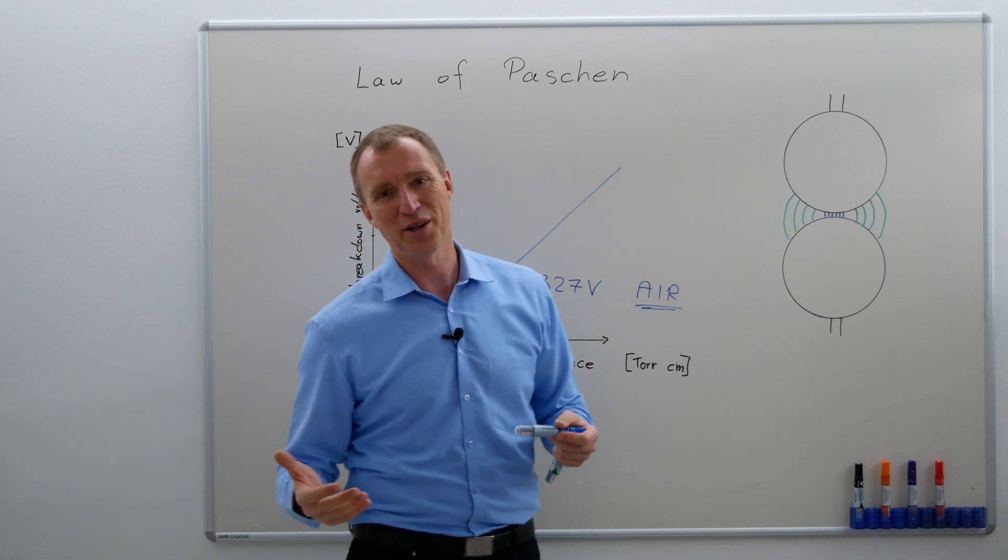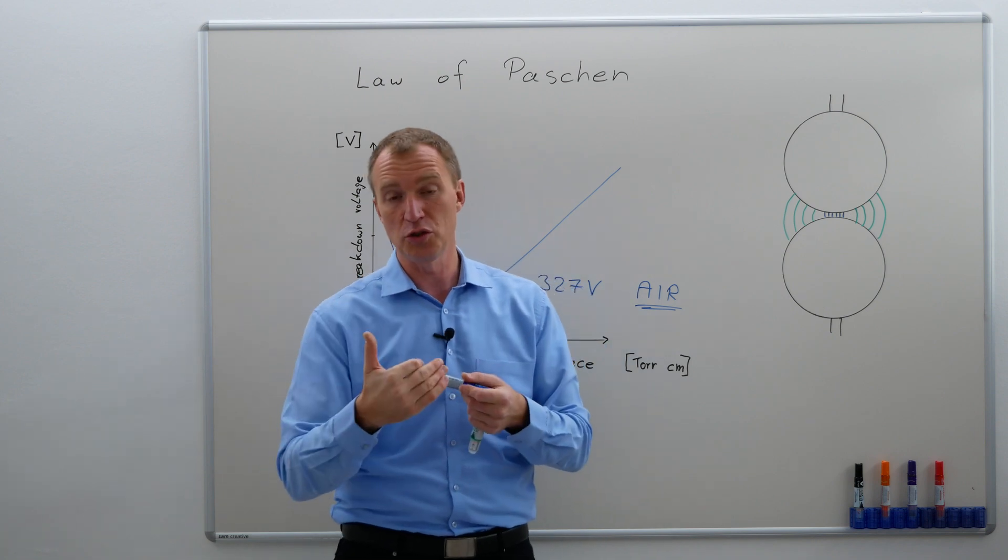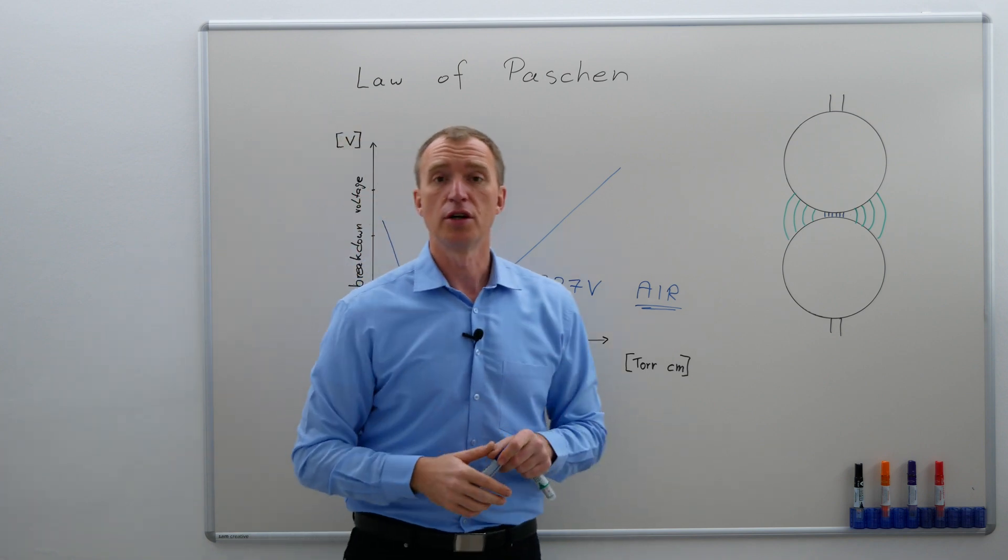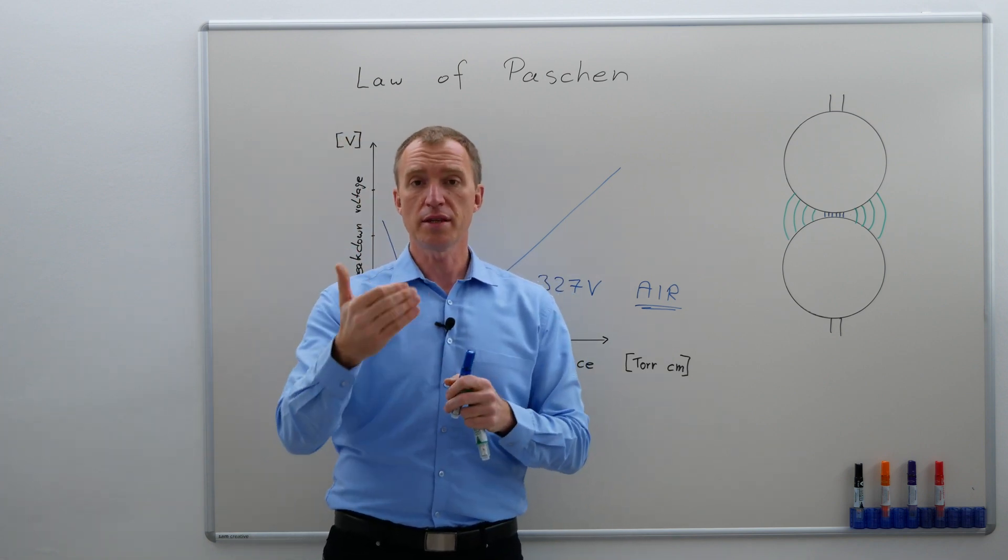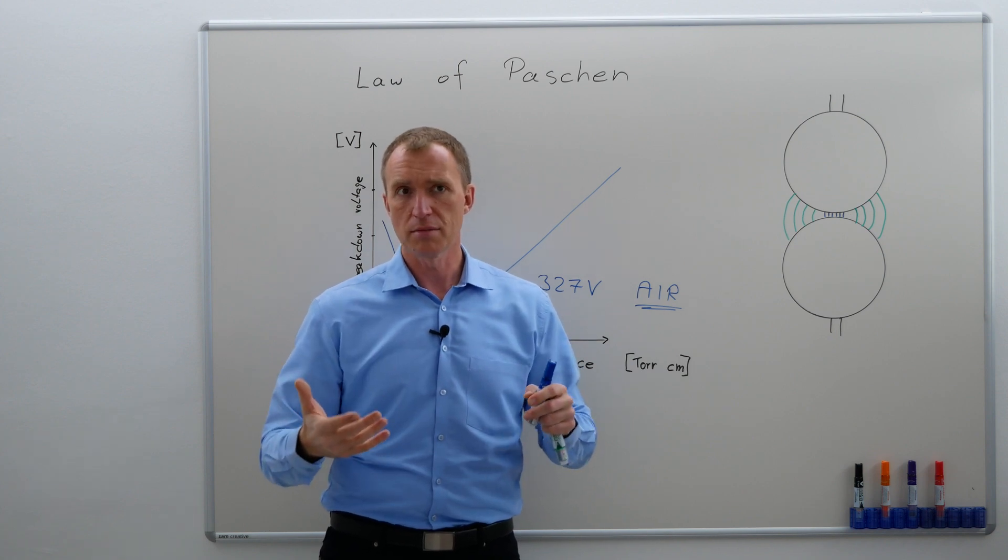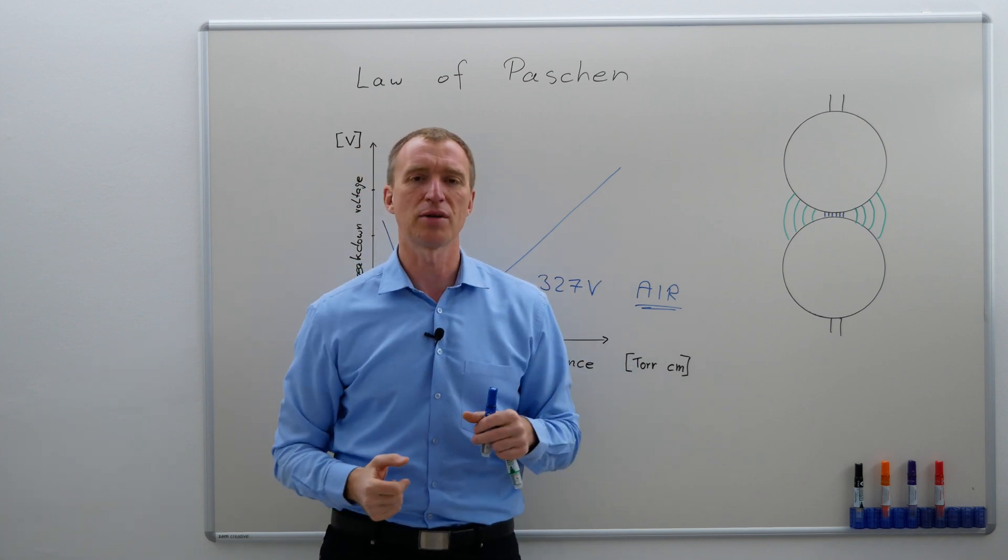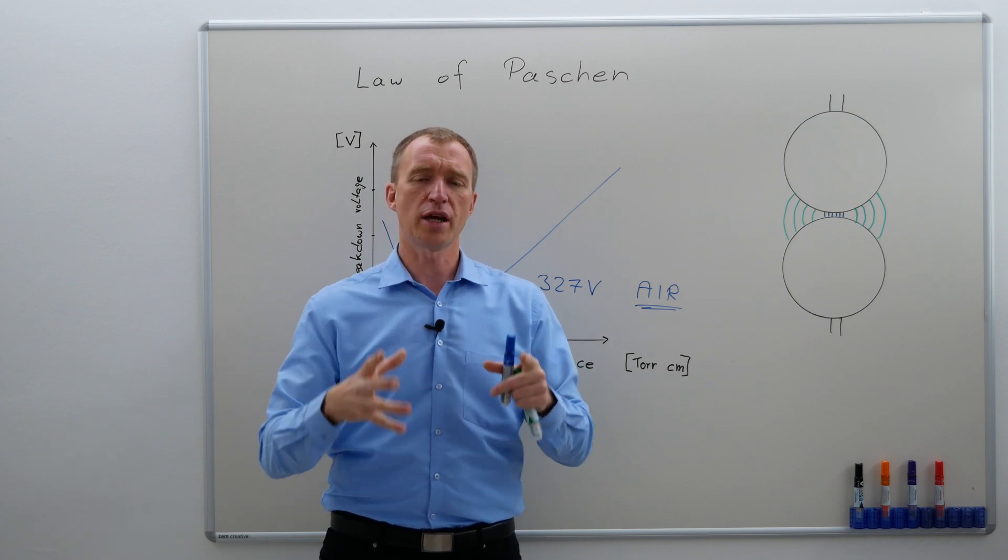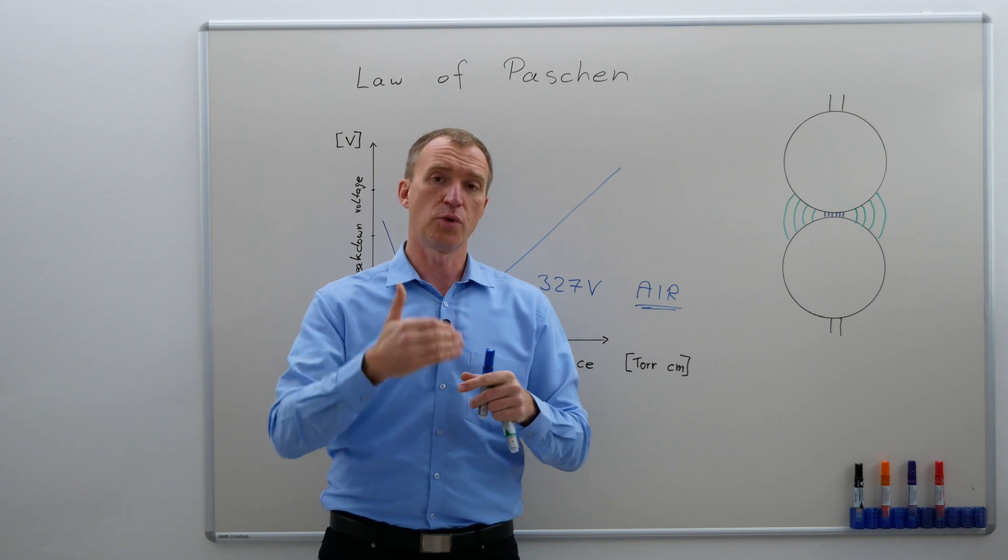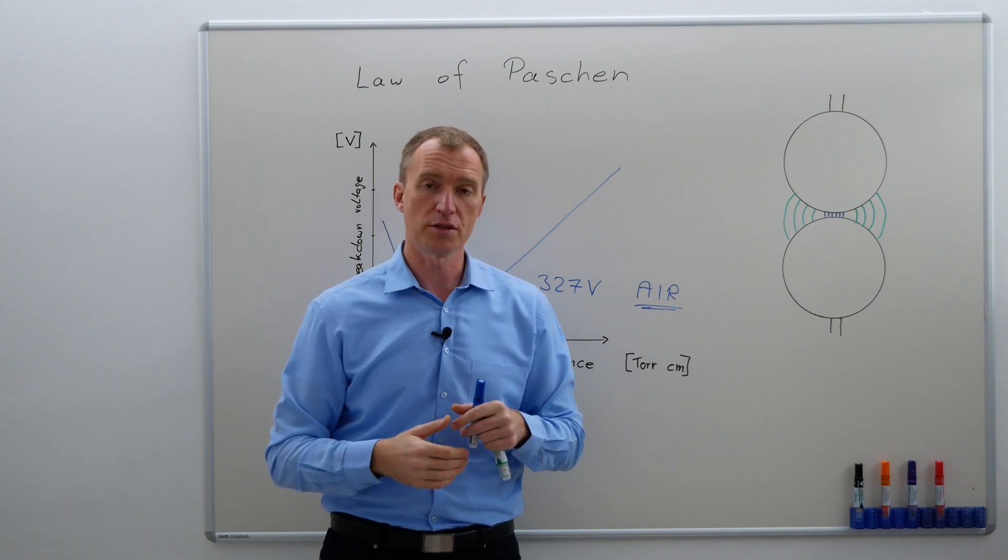Very often we don't have 7.5 micrometers in our world, especially not between two electrodes. Nevertheless, this helps us understand that changing the distance or changing the pressure will change the breakdown voltage, but it also changes the partial discharge inception voltage, meaning at what voltage level do we expect our first partial discharges.